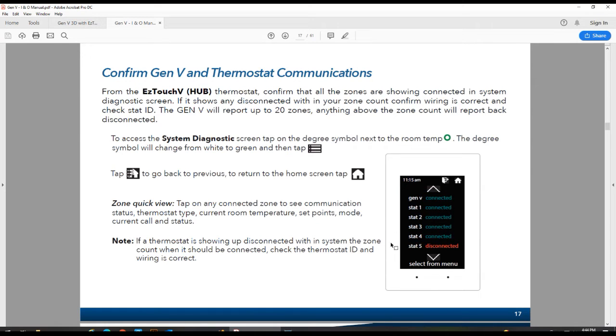If for whatever reason we are not communicating with any of the thermostats that we should have, you'll see disconnected. This is an indicator that we either have a wiring or polarity issue, or we have a stat ID conflict. So go ahead and make your way to that thermostat and address them accordingly, whether it be an ID or wiring issue. If at any time you need any help during startup or any questions, you can call Zonex Tech Support, and any one of the techs should be able to help you troubleshoot and work through any problems you're running into.